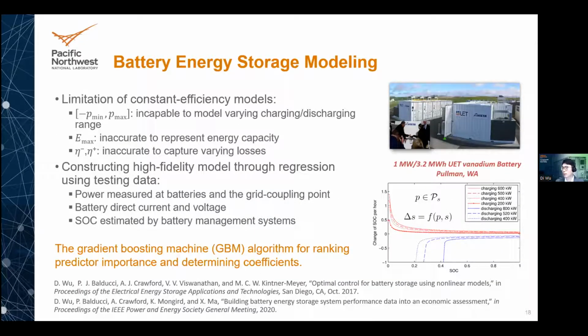For battery energy storage, we need to model operational flexibility and degradation effects. A constant efficiency model with static operating range is the easiest and most popular method to model operational flexibility. However, such a model may not fully capture operational characteristics of battery energy storage, especially for flow batteries. For example, here is the change of state of charge with different charging and discharging power levels for a 1 megawatt, 3.2 megawatt hour UET vanadium flow battery system.